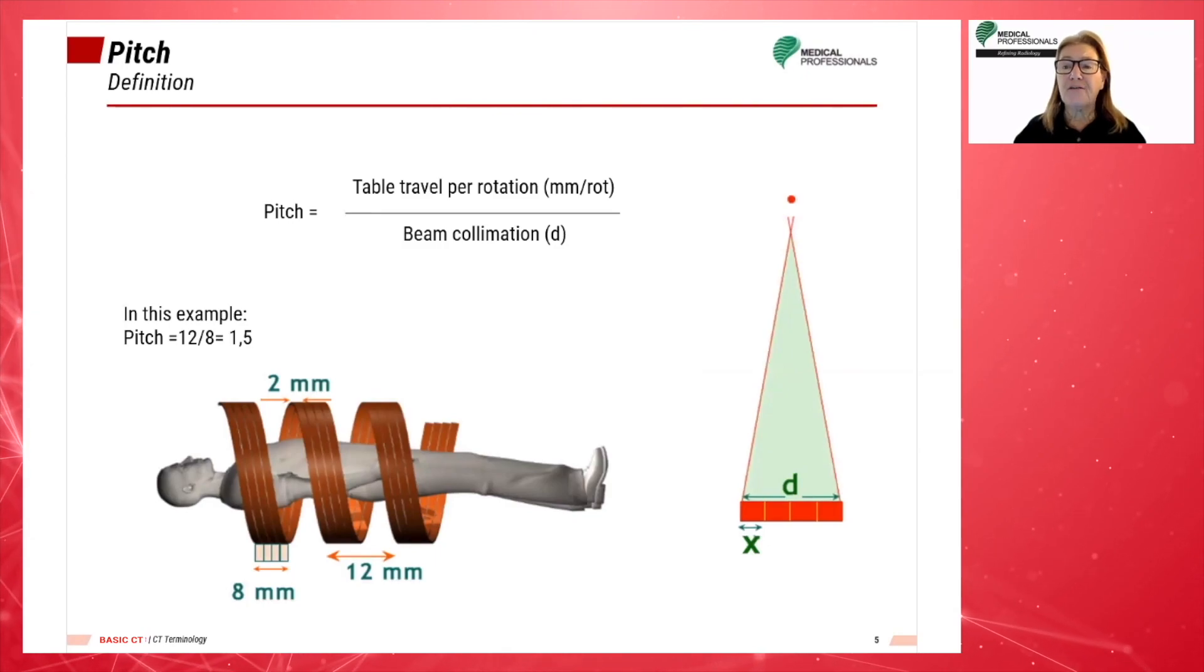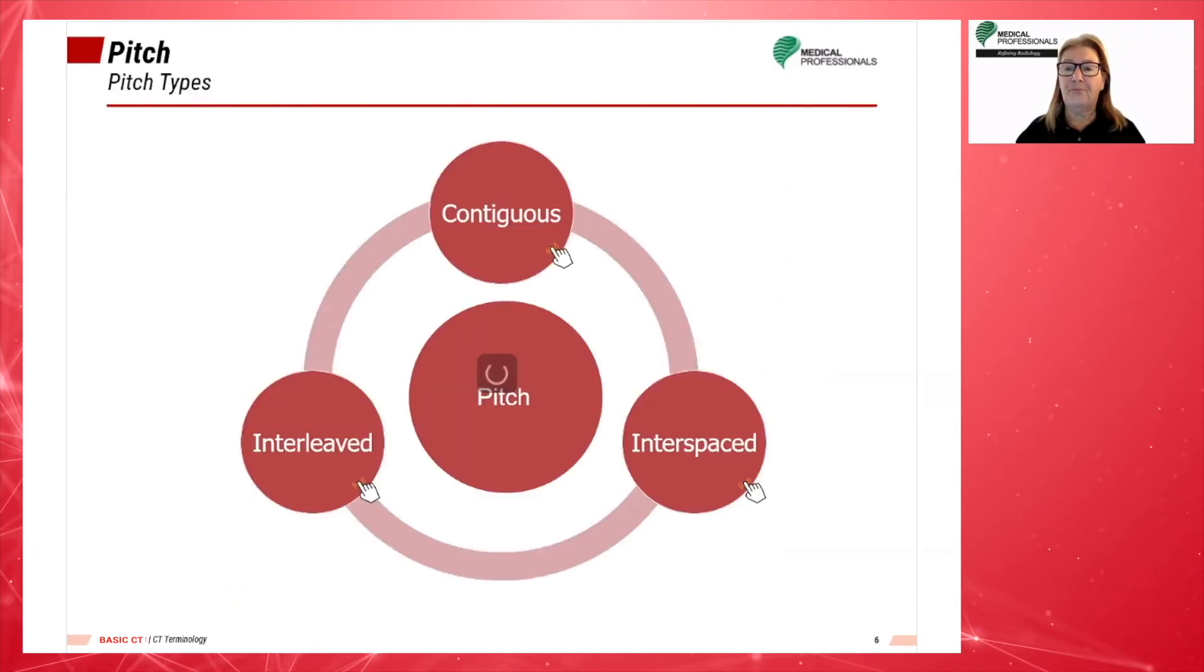Pitch is defined as the table distance traveled from one 360 degree gantry rotation divided by the beam collimation. Pitch plays an important role in image quality as well as in patient dose. Let's look at how.